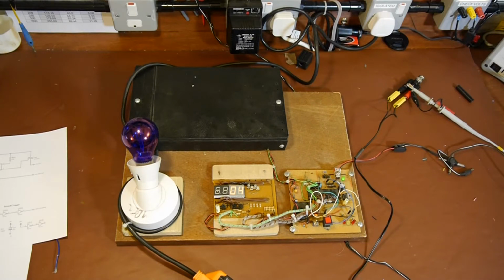So what we needed was a piece of test equipment where we could vary the power supply and cause some short power interruptions, so this thing didn't constantly falsely trigger and move the contents from RAM into E-squared just because of noise on the mains or fault conditions. This is a piece of equipment I knocked together very quickly in about a morning just so we could do some testing.